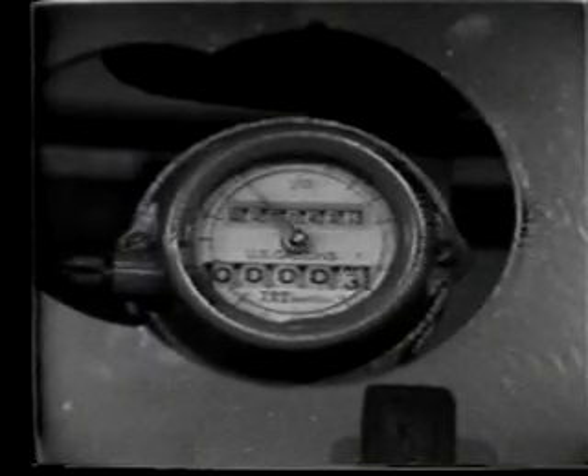The last component of the electrical system that we will consider is the flow meter. The flow meter has an impulse switch that is used to indicate the 1-inch fluid flow from the hydraulic control manifold to the BOP. The impulse switch sends voltage to an electrical relay circuit, which then sends count pulses to a counter in the remote panels. This counter then feeds the signal into the flow meter on the panel, and the meter registers the fluid flow.